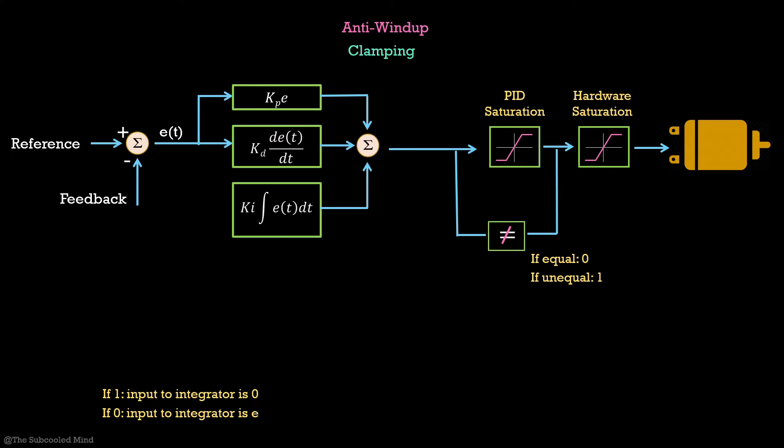But there is one more condition. Let us say that the PID controller is saturated but it is actually trying to decrease output, or in other words, it is trying to come out of saturation. At that moment, you do not want to stop the integrator. Hence we add another if condition to account for this.